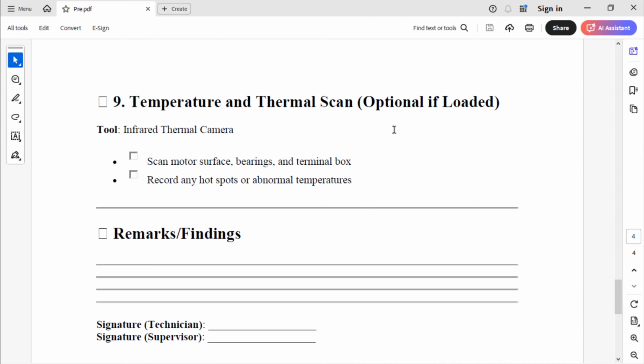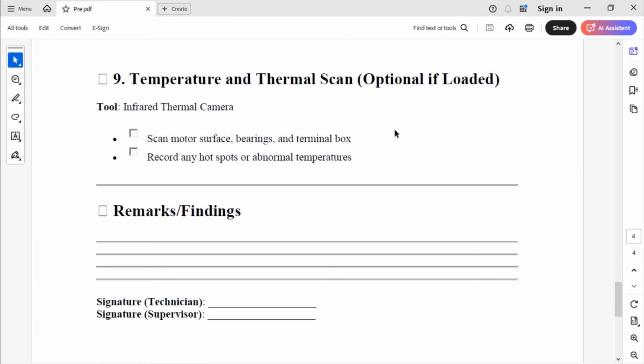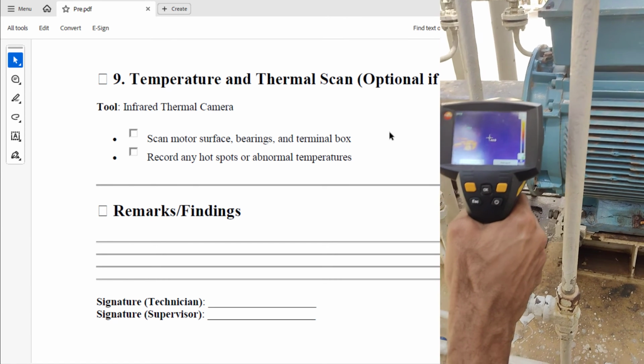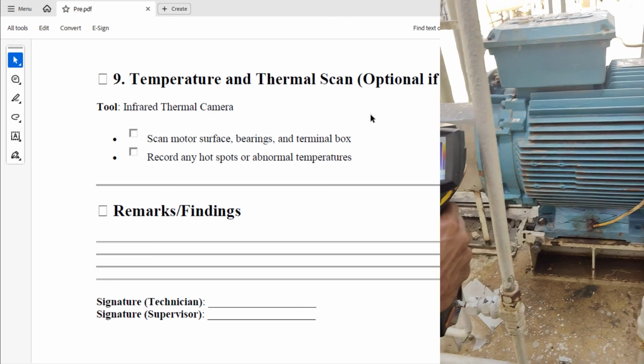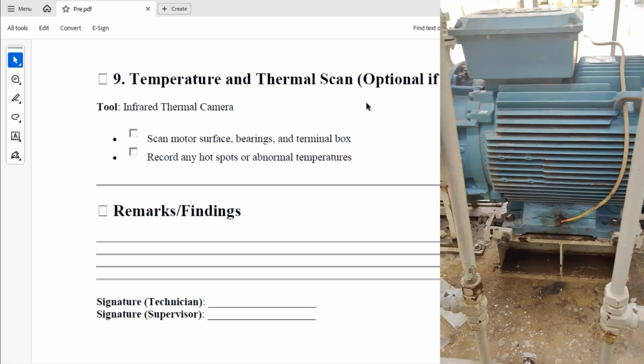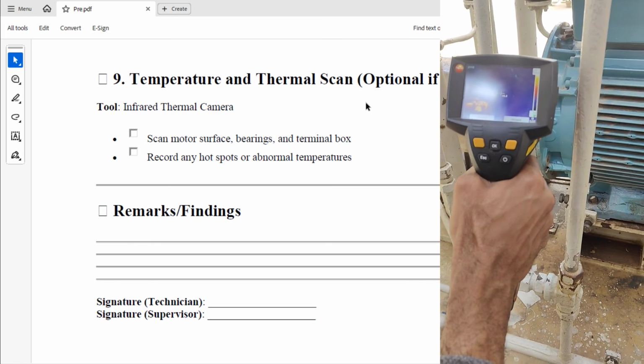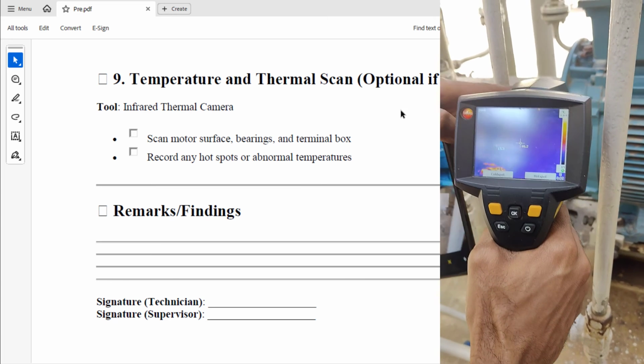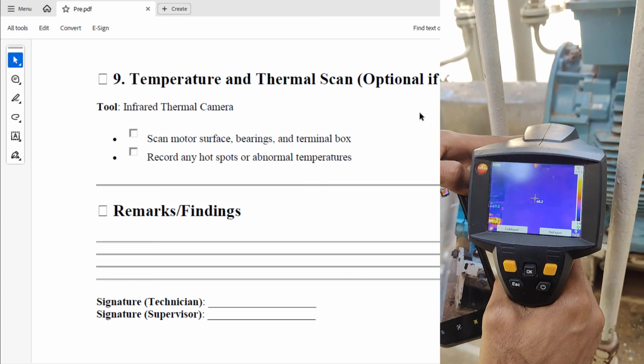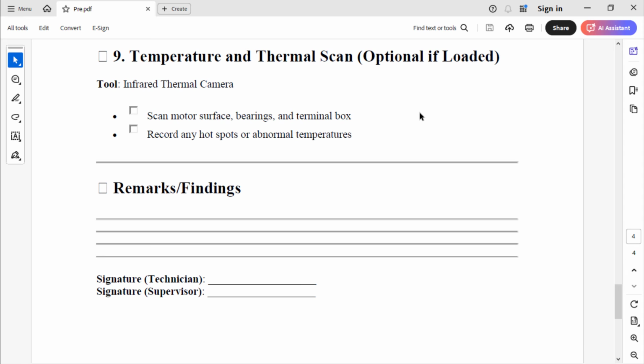Now let's go to the motor while it's working and check for temperature and thermal scan. We bring a thermal image camera, and check the windings while the motor is working, and check the connections, check the bearings, and this is considered predictive maintenance, not periodic maintenance. This was a complete checklist for a periodic maintenance for a low voltage 3-phase induction motor.